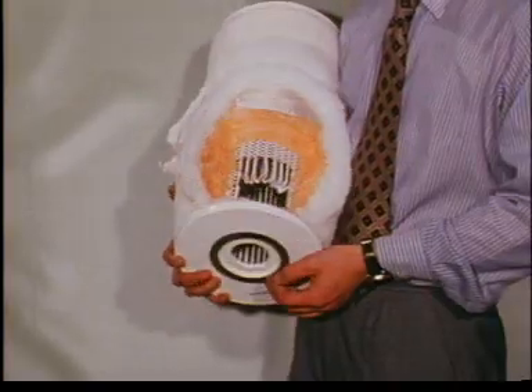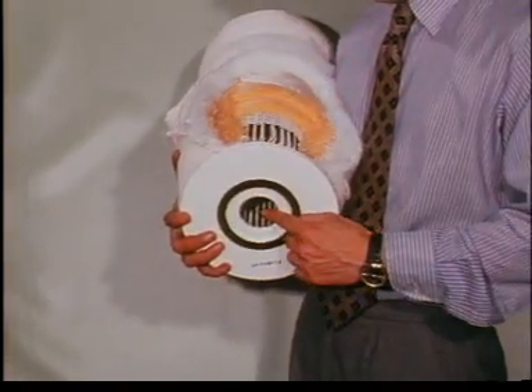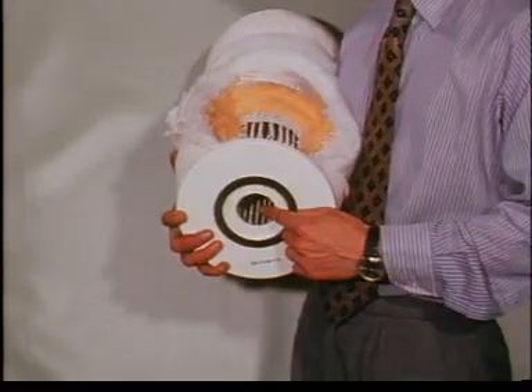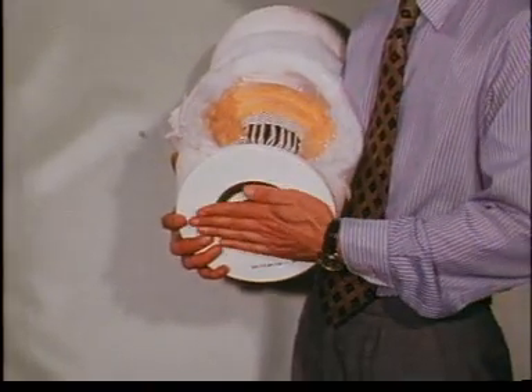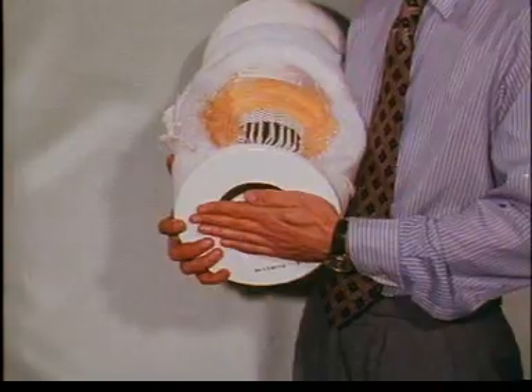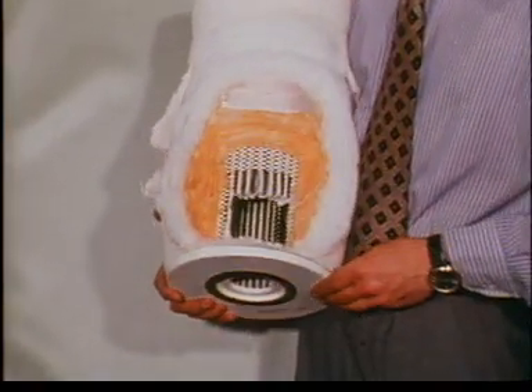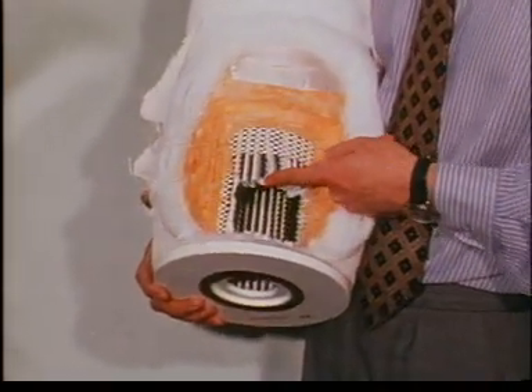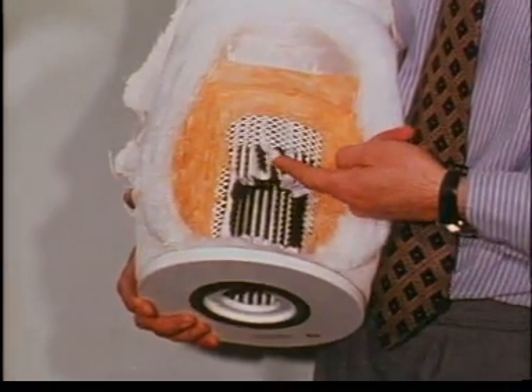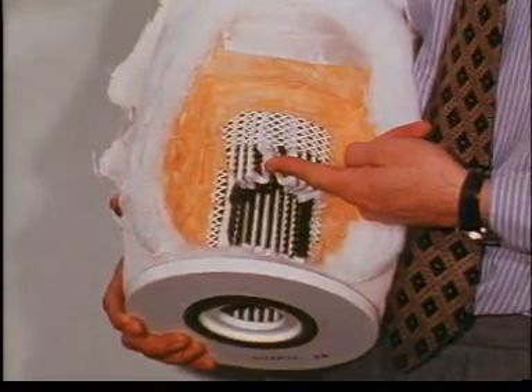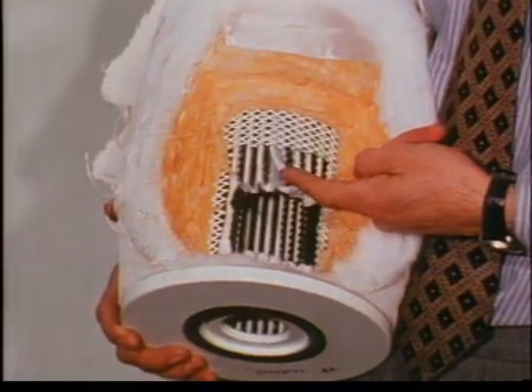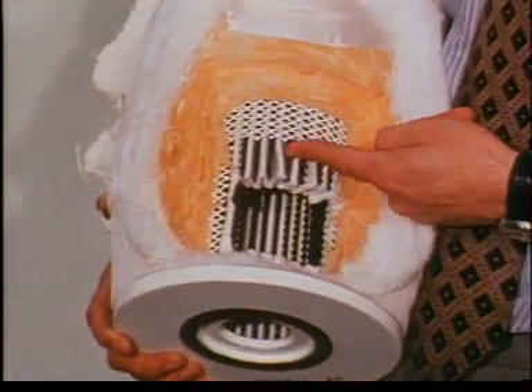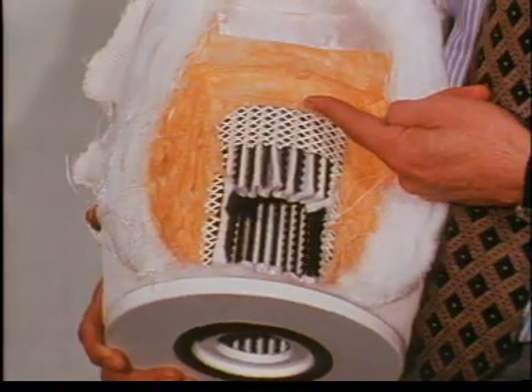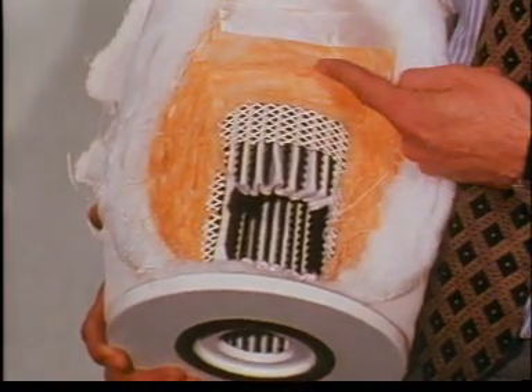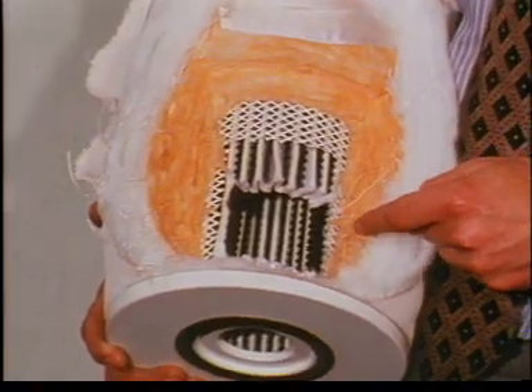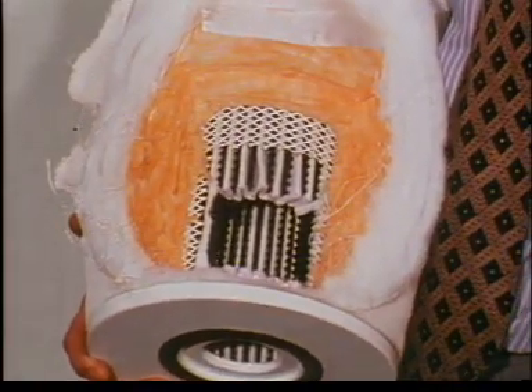In this type of coalescer, the oily water is fed into the bottom center of an element by means of a perforated pipe. The top and bottom of the element are sealed so that the oily water can only escape radially through the coalescer element. It first has to pass through a crimped screen of needle felt. This does not impede either the oil or the water, but collects any particles of solid matter that may be suspended in the mixture. The oily water then has to pass through a series of glass fiber concentric cylinders with perforated formers between them. Water passes easily through these, but oil is to some extent impeded.